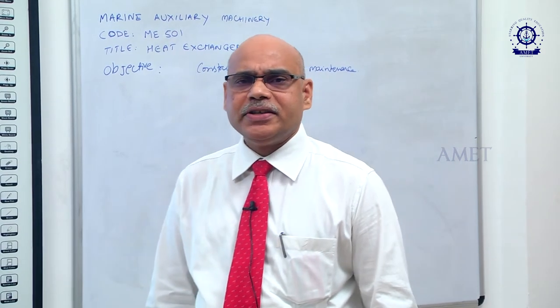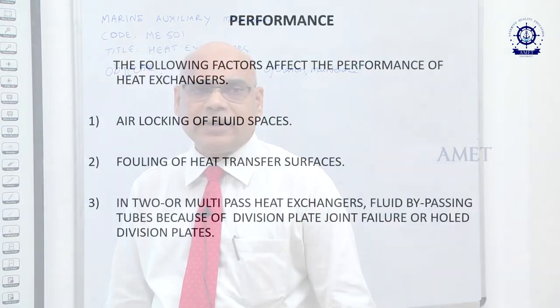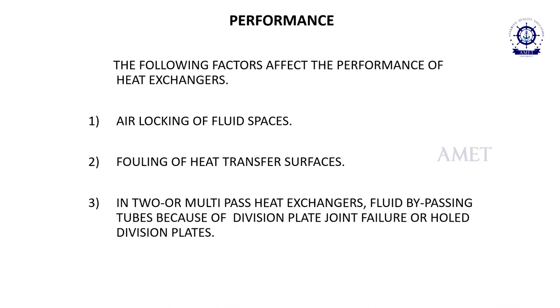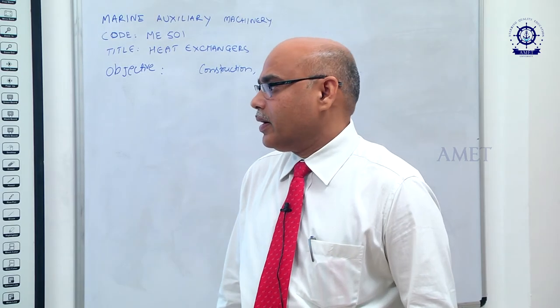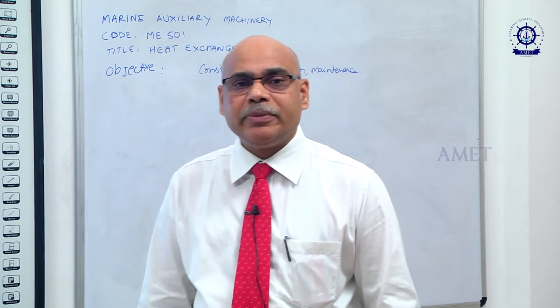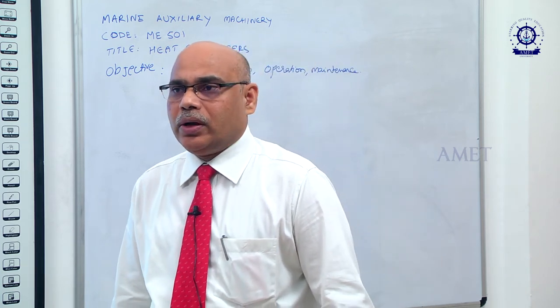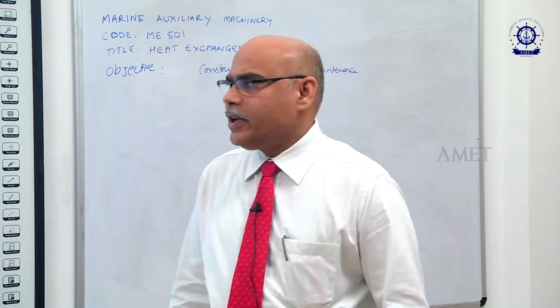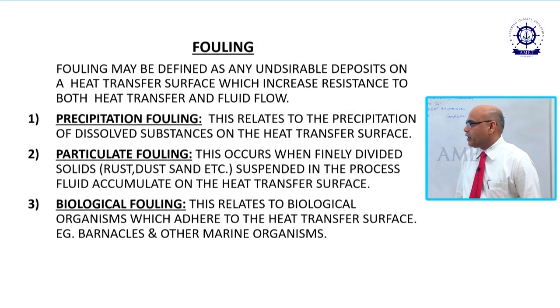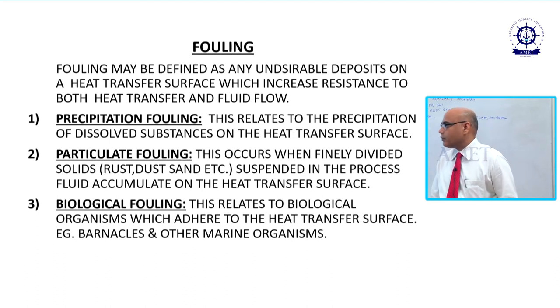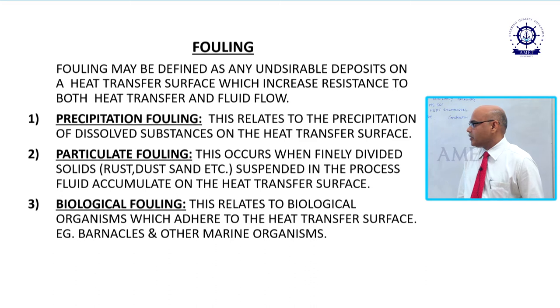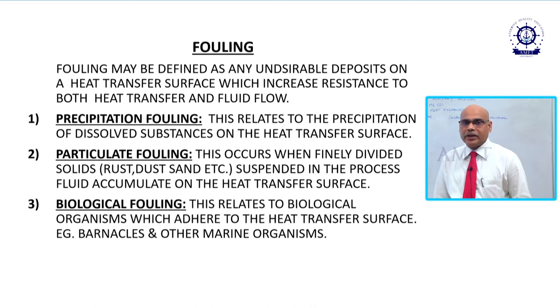The performance of the heat exchanger is affected by various factors: air locking, fouling, and sometimes the division plate gets a hole. In the fouling case we have biological fouling, particulate fouling, and precipitation fouling. The tubes get choked with this fouling, which affects heat transfer.